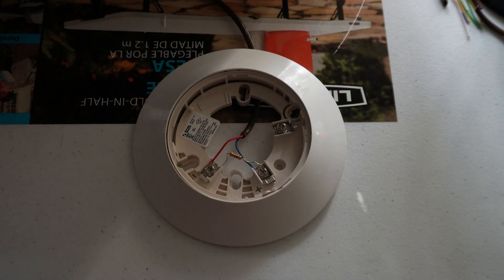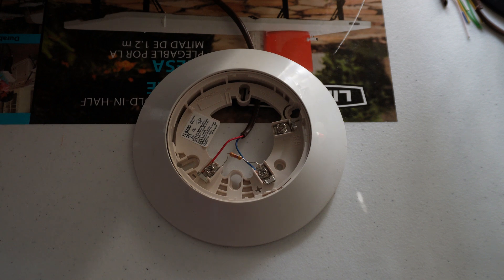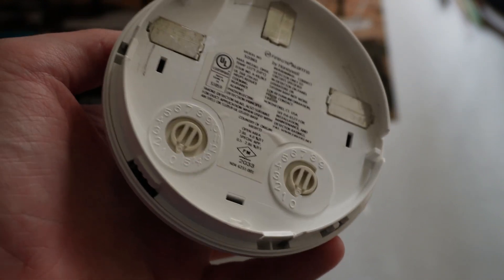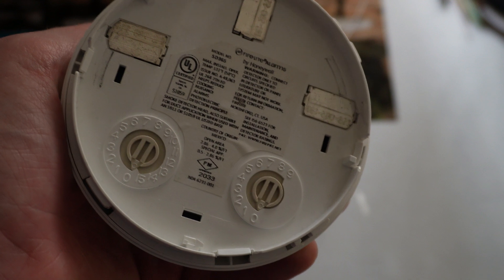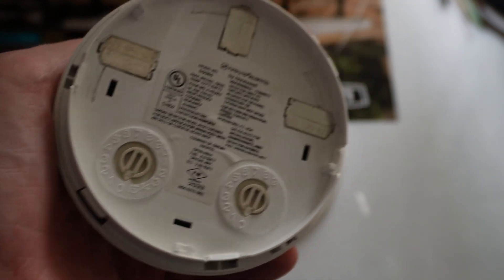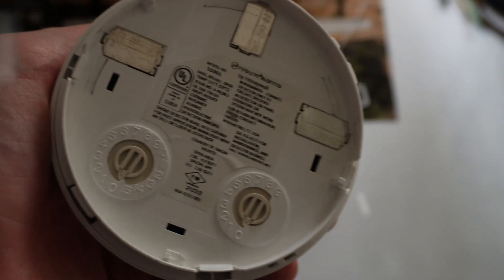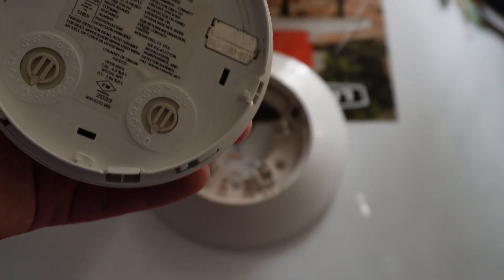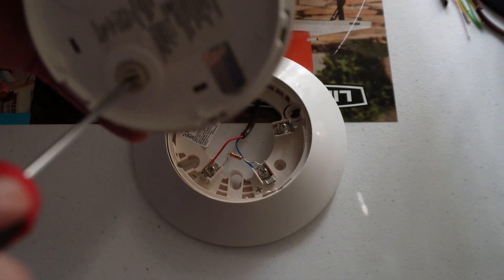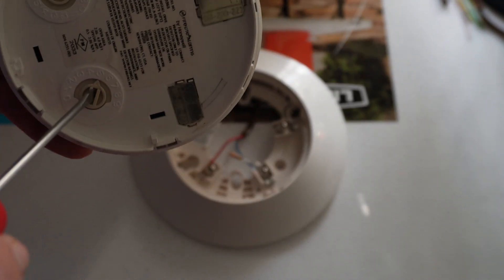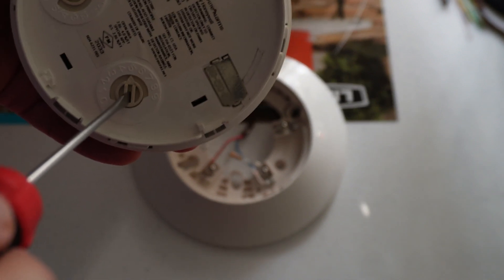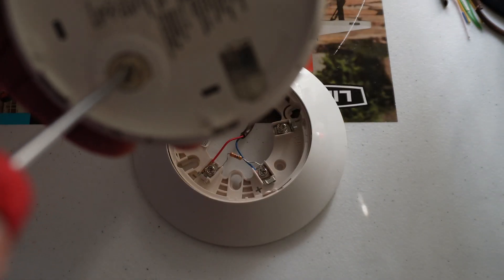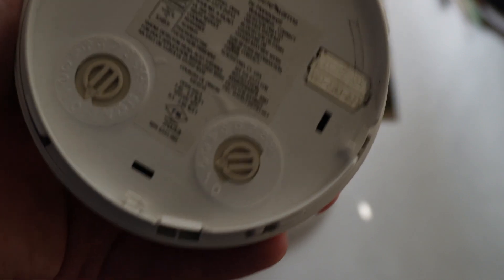The last thing we have to do before putting on the smoke detector head is we need to set an address on it, just like on the pull station. On the back of the smoke detector head, those two knobs are the address knobs. It doesn't have it labeled here for some reason, but usually this side is tens and this side is ones. I'm going to use a flat head screwdriver to turn the knob. Since we already have a device that has address one on it, I'm going to make this simply address two.